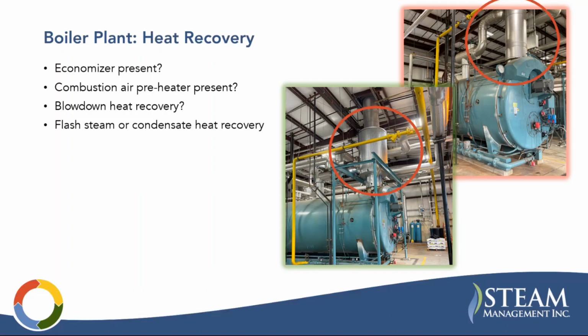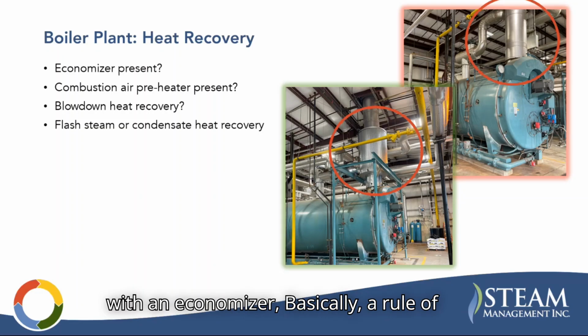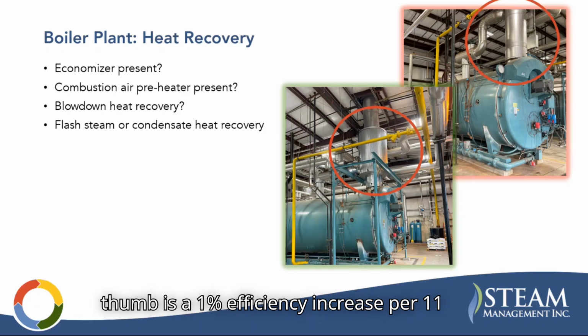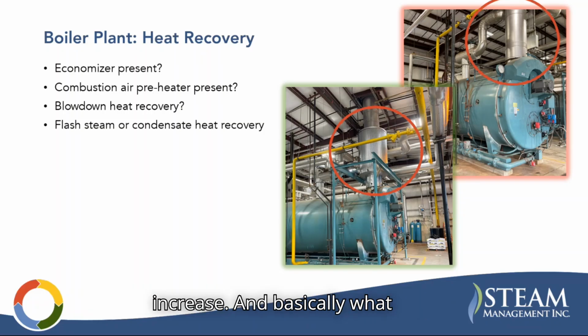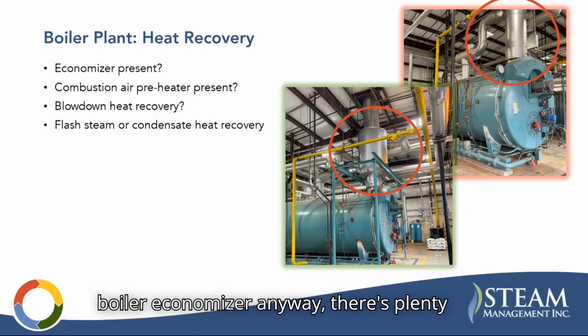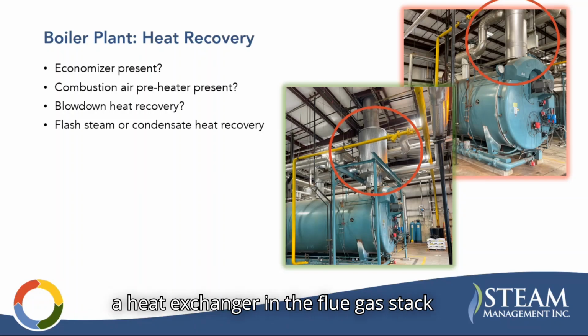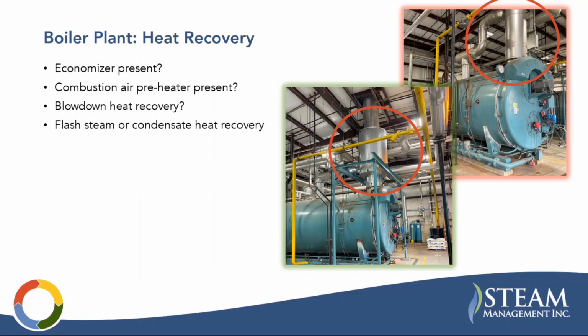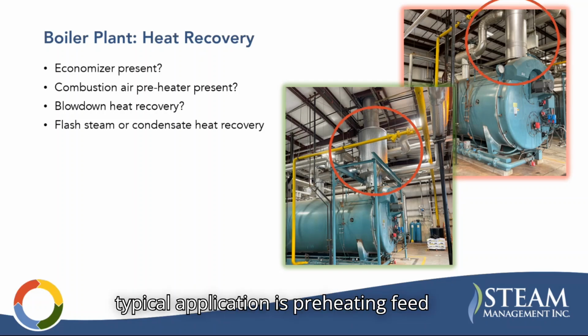And I should mention, with an economizer, basically a rule of thumb is a 1% efficiency increase per 11 degrees of feed water temperature increase. And basically what an economizer is: it's a heat exchanger. There are plenty of different types of economizers, but generally when you're talking about a boiler economizer, you're talking about a heat exchanger in the flue gas stack that is heating some process. Typical application is preheating feed water before the boiler.